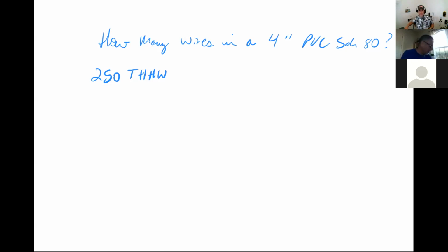I'm going to take Table 4, right? We're going to go to Table 4. So I'm on page 682. I always get these two mixed up because the Schedule 80 is at the bottom, and I expect 40 to be first and 80 to be next, but it's the other way around. So the 80 comes first on the bottom of page 682. Schedule 40 is at the top of the next page, 683. At any rate, we're typically looking for a 40% number, because with more than 2 wires, 40% fill is generally the number we use.